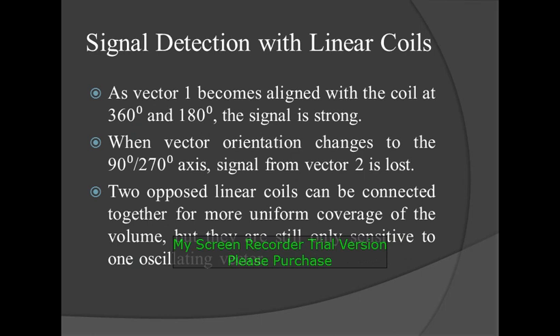Signal detection with linear coils: as vector 1 becomes aligned with the coil at 360 degrees and 180 degrees, the signal is strong. When the vector orientation changes to the 90-degree to 270-degree axis, the signal from vector 2 is lost. Two opposed linear coils can be connected together for more uniform coverage of the volume, but they are still only sensitive to one oscillating vector.